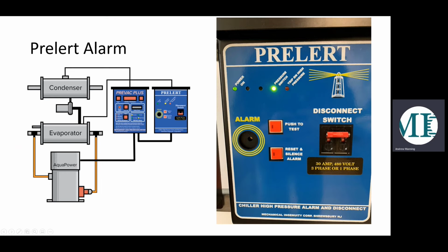Here we have the Prelert Alarm. So this is where the power comes in. And so we have the 30 amp breaker safety built in, and then we have the audible alarm for the overpressurization warning. So that's reading the evaporator pressure. So that alarm is going to sound at 10 pounds, and then that's going to alert maintenance personnel before the bursting disc goes at 15 pounds. And as you can see, that's the pressure switch that we have on the evaporator that we showed you before in the component list.